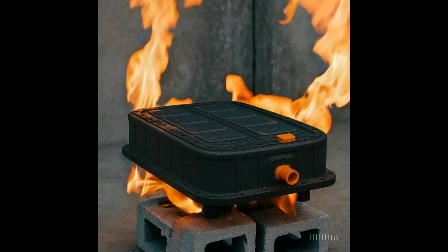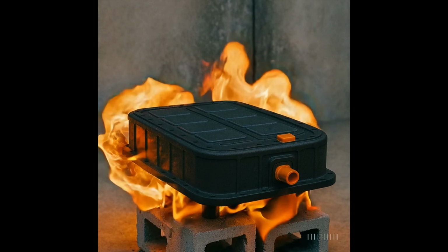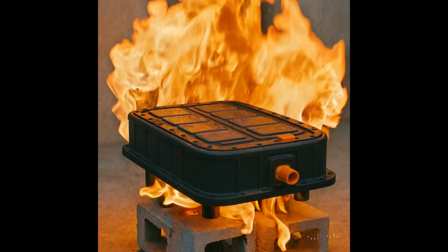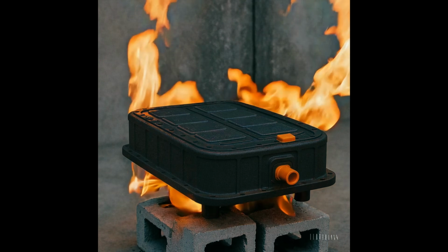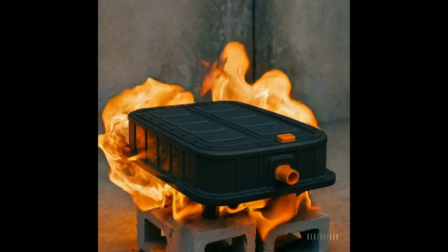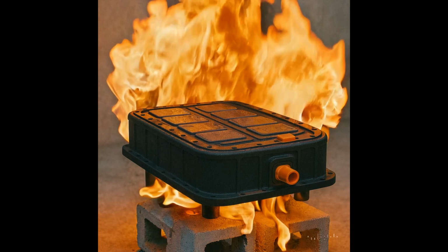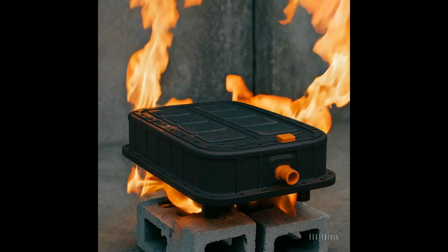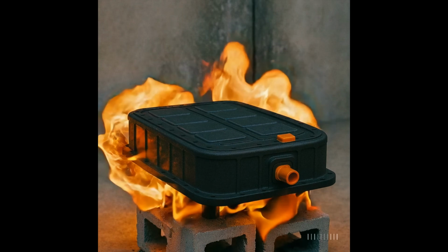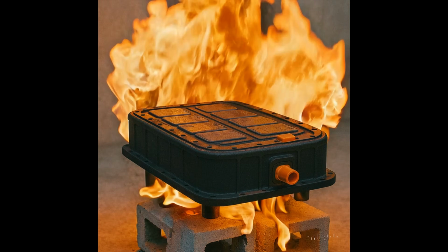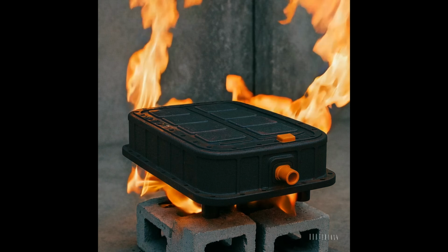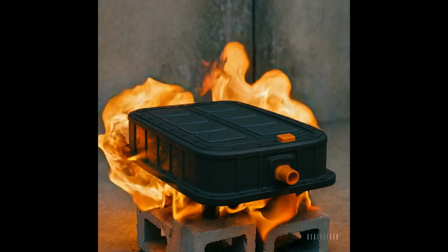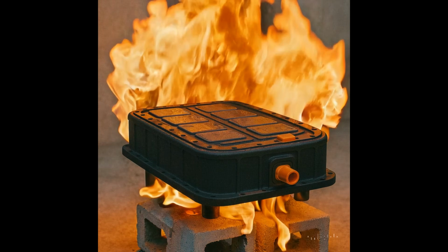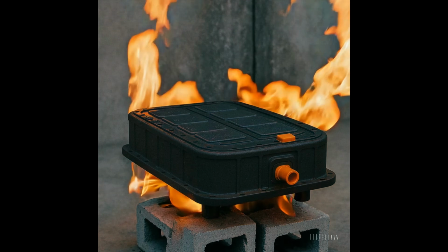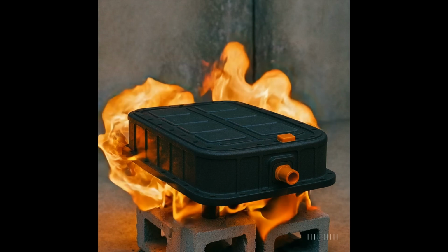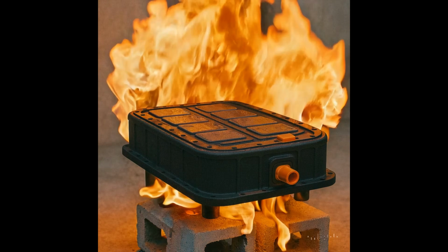Measurements include time to first cell venting, time to thermal runaway if it does occur, magnitude of explosion or flare, structural containment behavior, flame penetration into the enclosure, and post-test pack behavior. Did the safety vents function as intended, for example? Failure modes for external fire include rapid thermal propagation due to heating of metal casings, gas expansion and case rupture, or even explosion, failure of burst discs or flame arresters, and burn through of aluminum housings at sustained temperatures. Remember, lithium-ion packs contain flammable electrolyte, pressurized gases, and hundreds or even thousands of individual cells. If the pack ignites violently, it can escalate into a vehicle fire exponentially.